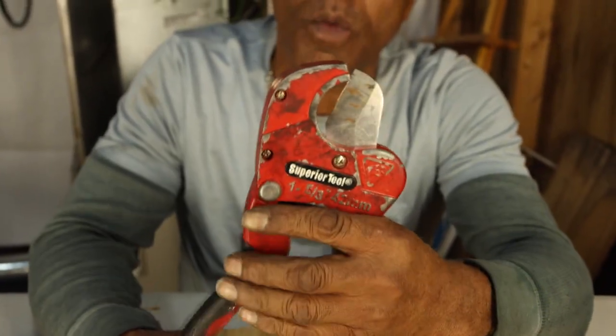We often need it. A lot of the tools that we're dealing with and showing are more so used in installs. As a service tech, install isn't really what you do, but sometimes you need to replace. See, if I go to an air conditioning system that isn't working, if it was working, that means the electricity has already been run to it. The refrigeration copper has already been run, and there's already been an inspection. As long as I'm not running new power to that unit, I can change it out as a service provider.